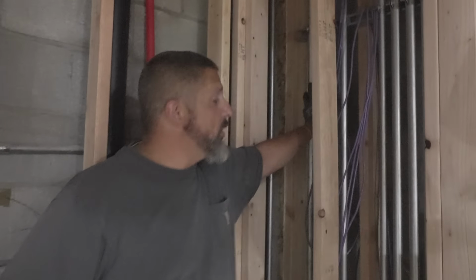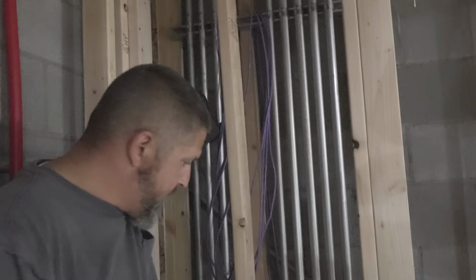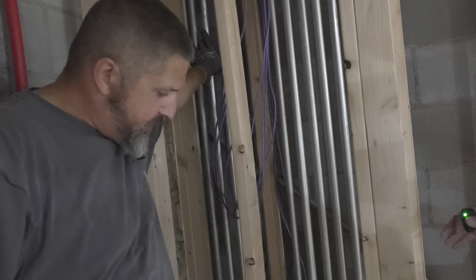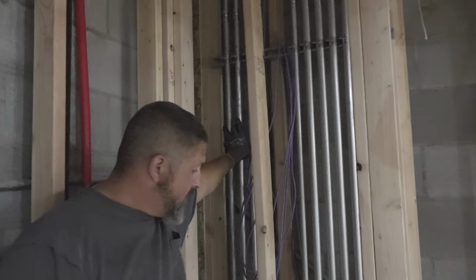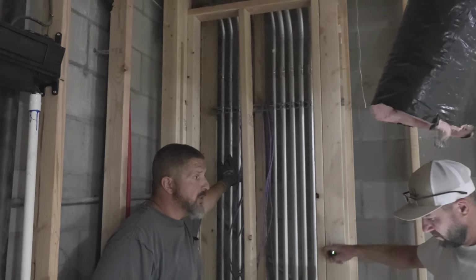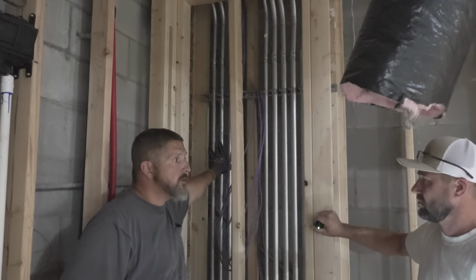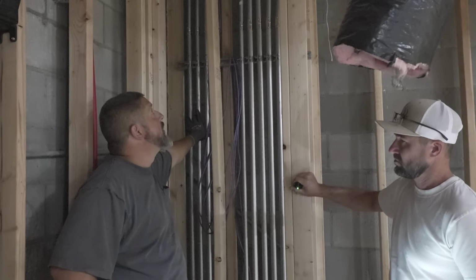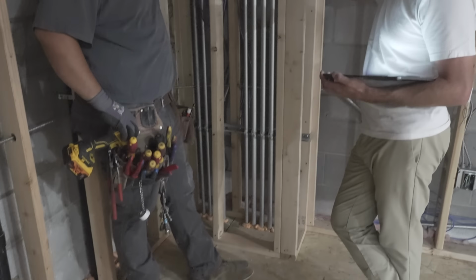So coming through here, what do we got over here? These conduits come out of H1A, which is a high voltage panel, 277/480. It sits downstairs. It used to run a bunch of the old ERV panels. Back up so you can kind of see them a little bit. They used to run the old ERV panels when they were up on the roof. Plans changed after piping was in. And so now it's a bunch of spares to our 480 going downstairs.